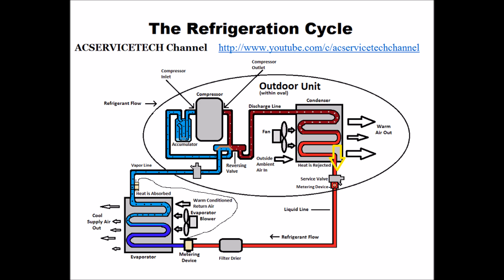That's how we check the refrigerant charge of a system in cooling mode that has a thermostatic expansion valve at the evaporator coil.